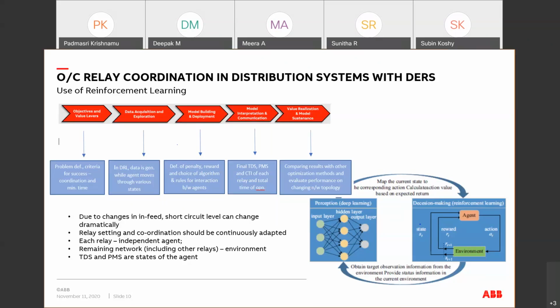Basically, what happens is, because of the presence of in-feed, the short circuit level can change dramatically, because of which the coordination of the overcurrent relay may fail. Because, as we mentioned, the distributed generation can go on and off in a system, and because of that, the short circuit levels and the fault current paths can be different. Hence, it is really required to have an adaptive relay coordination strategy.